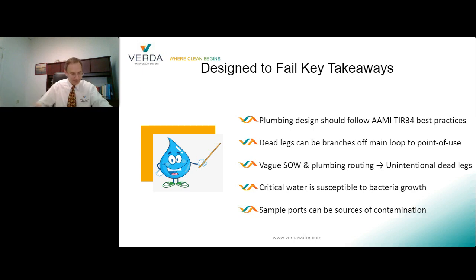At this site, we saw an ultrasonic that was plugged into a wall outlet, and since that outlet was ground fault protected, it got splashed by water and it tripped, turning off the UV light. For how long, no one knew. So a key element for controlling bacteria growth in the system was off and unchecked for potentially months. So again, you have to maintain the systems even if you're not, quote unquote, using it.